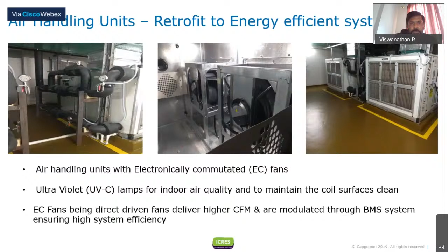And all the air handling units are controlled through the building management system. And this is the typical power comparison between a conventional AC motor and a retrofitted EC fan for a single AHU. If you can see, for a 17,169 CFM AHU, the conventional motor consumes around 11.2 kilowatt of power. But the retrofitted EC fans consume only 6.9 kilowatt of power, while delivering slightly higher CFM because of the direct driven fan.